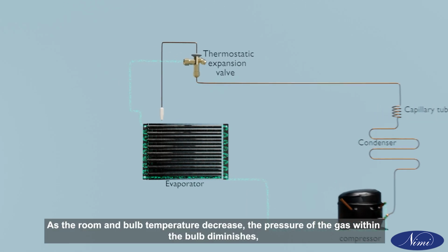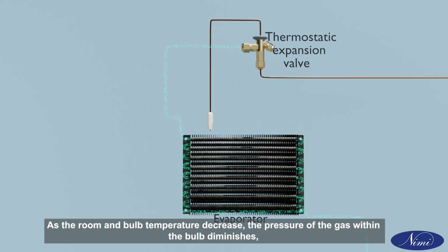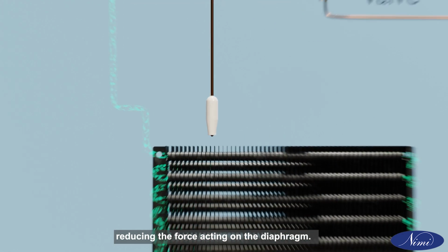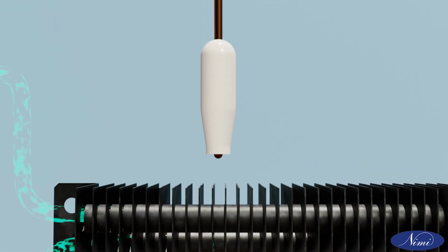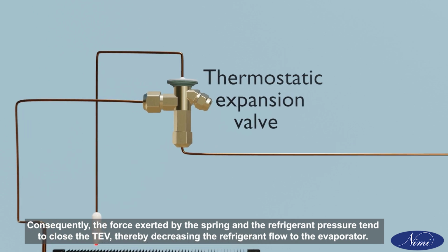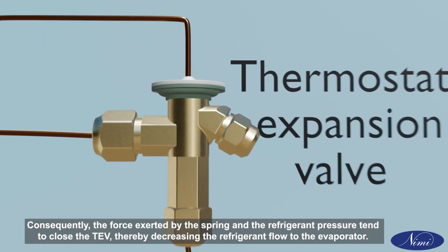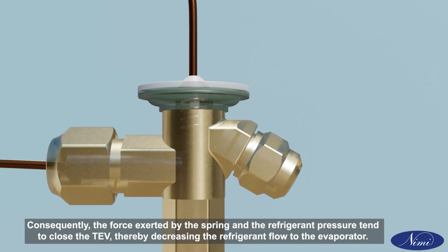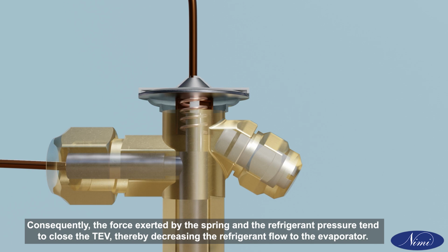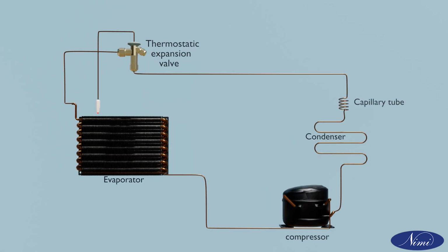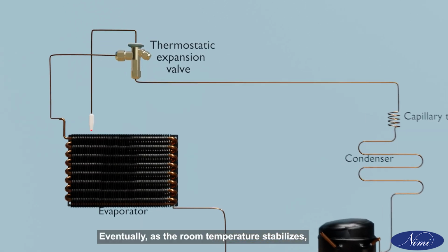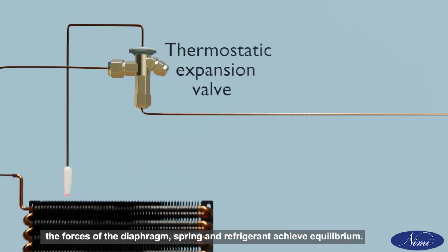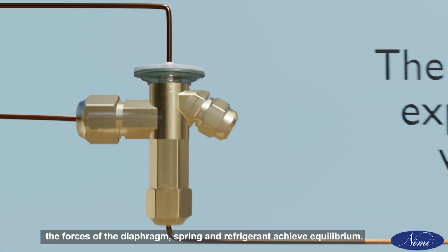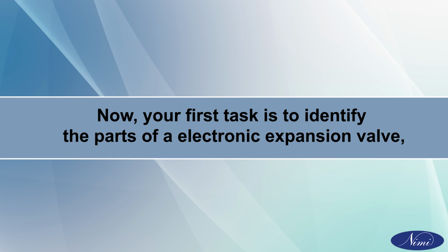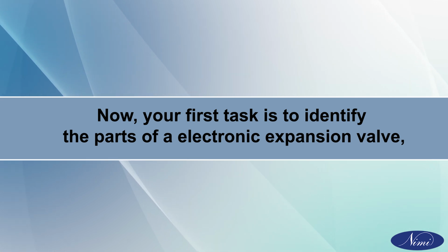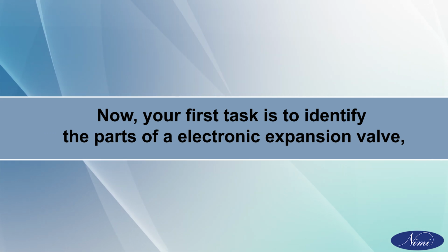As the room and bulb temperature decrease, the pressure of the gas within the bulb diminishes, reducing the force acting on the diaphragm. Consequently, the force exerted by the spring and the refrigerant pressure tend to close the TEV, thereby decreasing the refrigerant flow to the evaporator. Eventually, as the room temperature stabilizes, the forces of the diaphragm, spring, and refrigerant achieve equilibrium. Now, your first task is to identify the parts of electronic expansion valve.